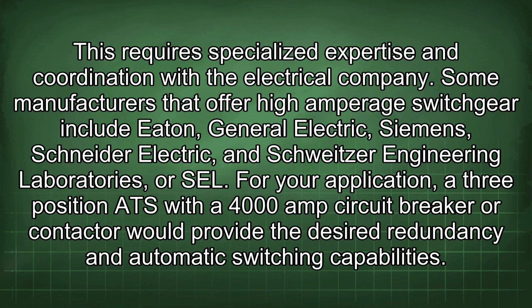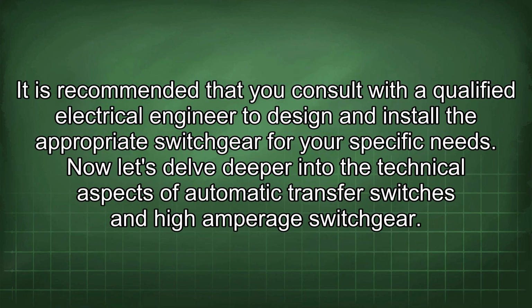Some manufacturers that offer high amperage switchgear include Eaton, General Electric, Siemens, Schneider Electric, and Schweitzer Engineering Laboratories, or SEL. For your application, a 3-position ATS with a 4000 amp circuit breaker or contactor would provide the desired redundancy and automatic switching capabilities. It is recommended that you consult with a qualified electrical engineer to design and install the appropriate switchgear for your specific needs.